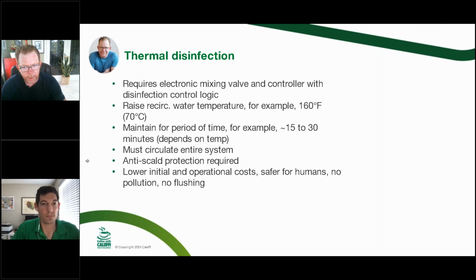So it does require an electronic mixing valve, and it does need to have a disinfection control logic built into it. It has to maintain that for a certain period of time. So typically it's 15 to 30 minutes, but again, it depends on what temperature you're at. As Tom Gervais liked to remind me, it's not a published number, but we all have those charts where we know how long it takes to kill this. So if I've got the water at 140 degrees, then guess what? It's going to run for 30 plus minutes. If Max has the water set at 180 degrees, it's going to be way less than that. But again, we have to be conscious of the fact that we can't have people trying to draw water off a tap at that temperature.